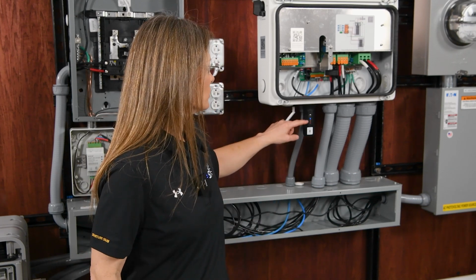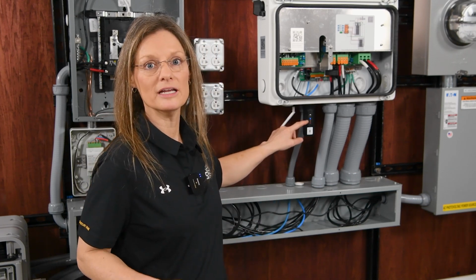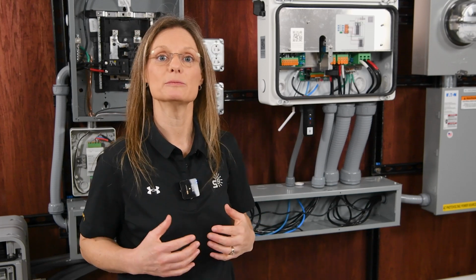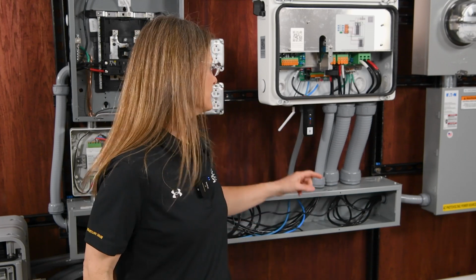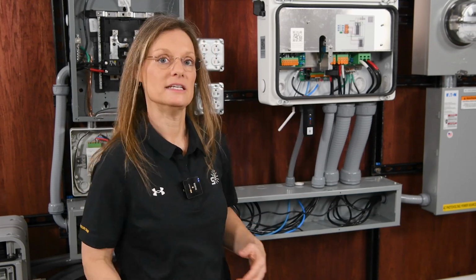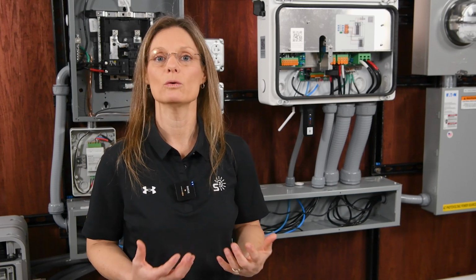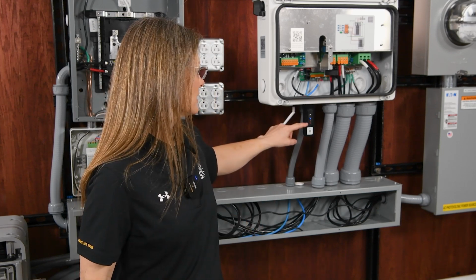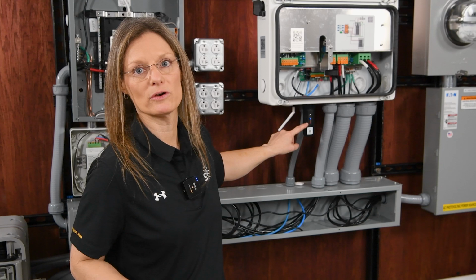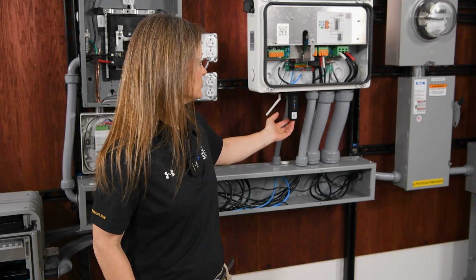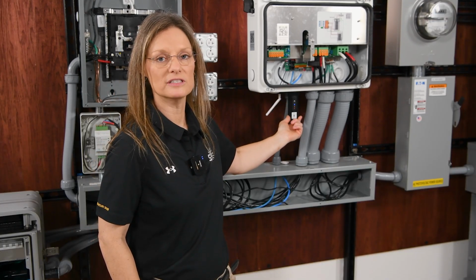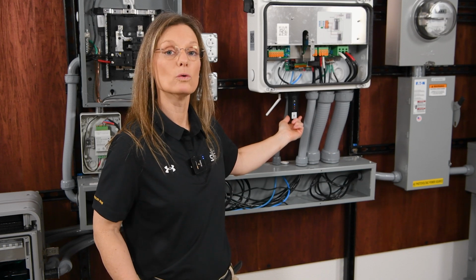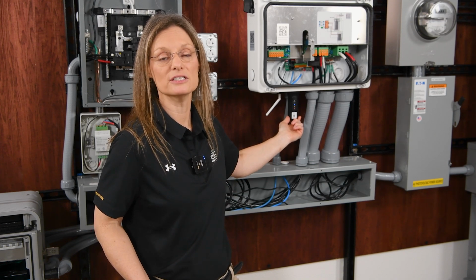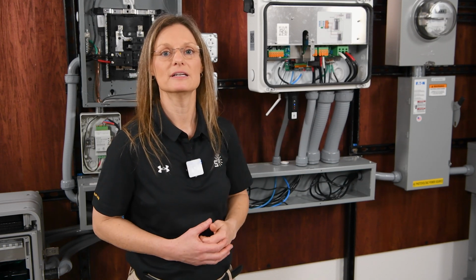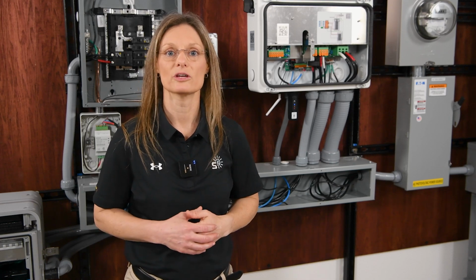Your next light will either be solid or it might be blinking every 5 minutes, meaning it is transmitting data. And this second light is yellow, meaning it is communicating with your inverter. And your last light should be red, meaning it has power. Then you have a reset button. If you should, for any reason, need to move this data logger to another inverter, or your password on your Wi-Fi changes, you may need to hold that reset button down for 10 seconds and go through the commissioning process again.